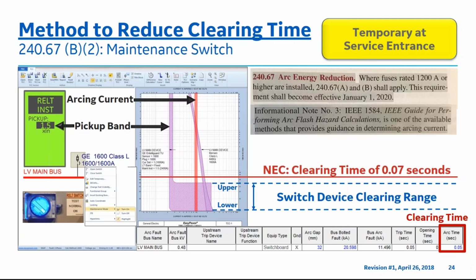Please notice that the arcing current is a vertical transparent red line shown in the center, and the pickup band is off to the left. An extreme hazardous condition could be witnessed if the arcing current directly overlays the pickup band. In other words, the red transparent line of the arcing current in the center is directly over the purple pickup band of the time current curve on the left, which is why experience with time current curves is necessary, as arcing faults can range from 29% to 79% of the bolted fault value in low voltage power distribution systems. Legal supervision as well as experience is required per the NEC language. I will highlight this language on the next slide as one of the notes.